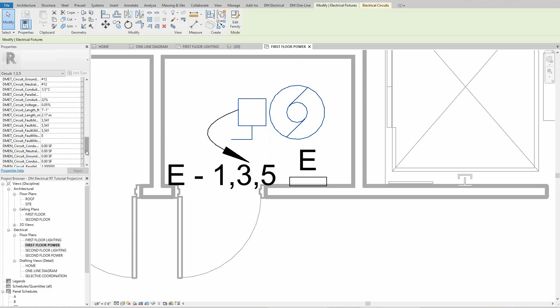To get the fault at a motor, you had to do a little bit of work with the modeling to get it to work out. Now every device can display what that fault is. That's included both in the shared parameters on the device itself, and then if we select the circuit, it is also included as shared parameters on the circuit fault values.